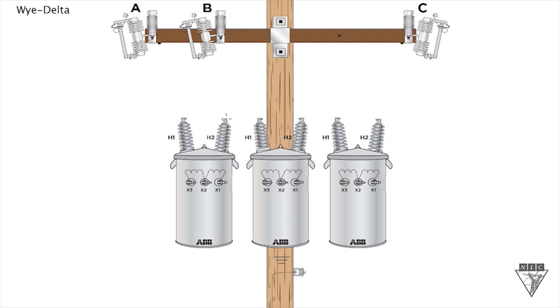So first thing we need to do is we need to take all our H2 bushings and connect them together. Once they're connected together, we're not going to tie it to ground. So a common saying with a Y-delta connection is Y-delta you float, meaning that the H2 bushings are connected together but they're not tied to ground.